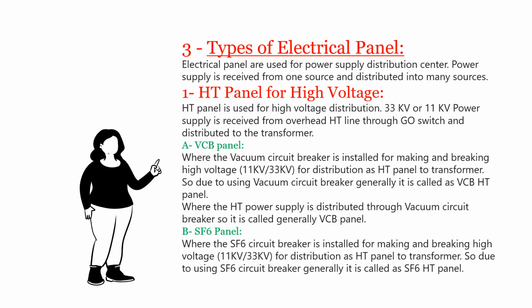Three. Types of electrical panel. Electrical panels are used as power supply distribution centers. Power supply is received from one source and distributed into many sources. HT panel for high voltage. HT panel is used for high voltage distribution, 33 kV or 11 kV. Power supply is received from overhead HT line through GO switch and distributed to the transformer.